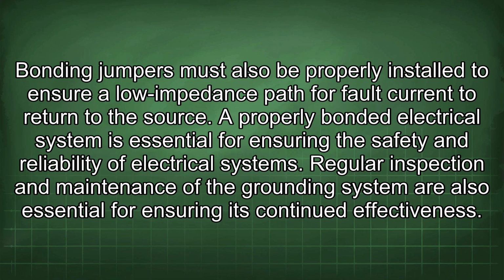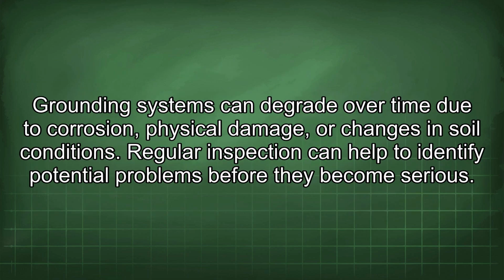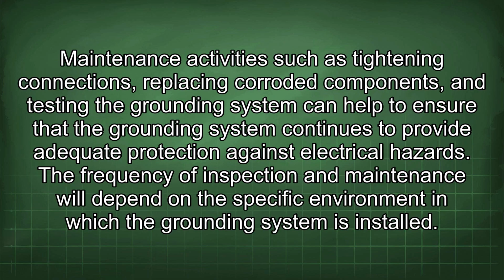Regular inspection and maintenance of the grounding system are also essential for ensuring its continued effectiveness. Grounding systems can degrade over time due to corrosion, physical damage, or changes in soil conditions. Regular inspection can help to identify potential problems before they become serious. Maintenance activities such as tightening connections, replacing corroded components, and testing the grounding system can help to ensure that the grounding system continues to provide adequate protection against electrical hazards.